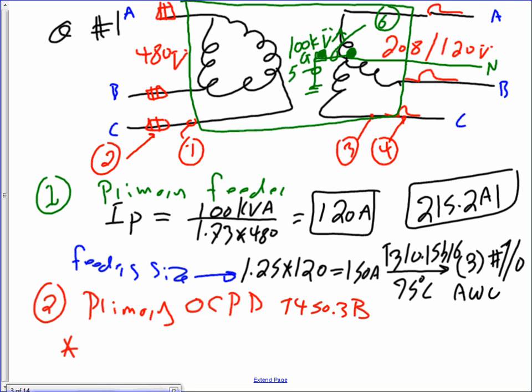AWG. And what type of insulation? Let's just assume that this conductor, guys, was indoor, and let's assume we're going to be using THHN. So we have 3 conductors. Why 3 conductors? Delta. Does delta need a neutral? Look at the delta. Is there a neutral on the delta side? No. Delta does not need a neutral. Any comments, guys? Any questions? Does it make sense? What's the 215.2(A)(1)? That's an NEC code book, NEC 2011. That's the size of your conductors.